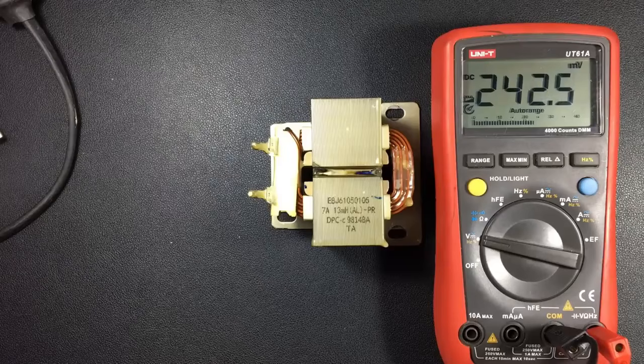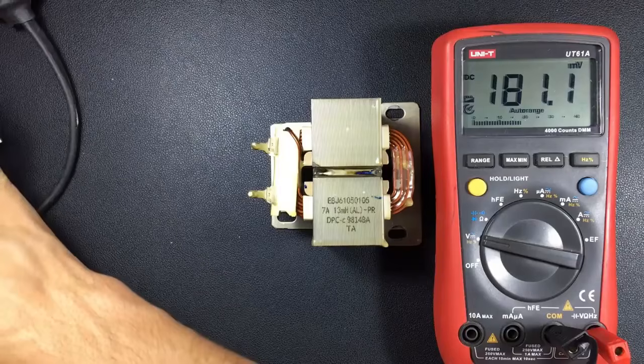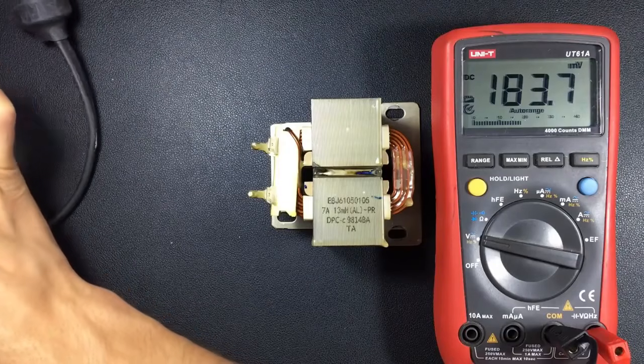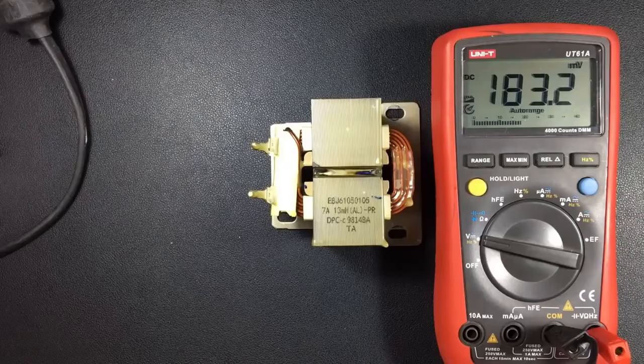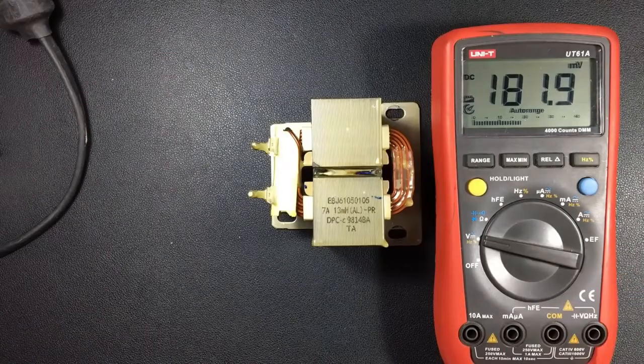If it starts to have resistance, we will have problems in an inverter electronic circuit, and those are the cases in which, for example, we have overcurrent errors. So if you have overcurrent error or even low voltage, check the reactor.